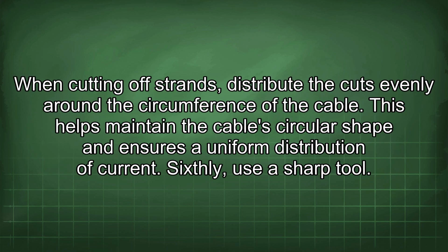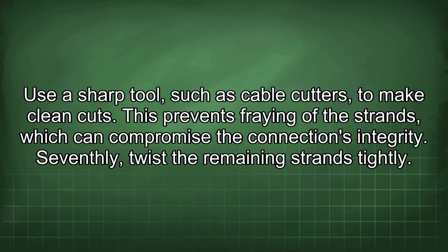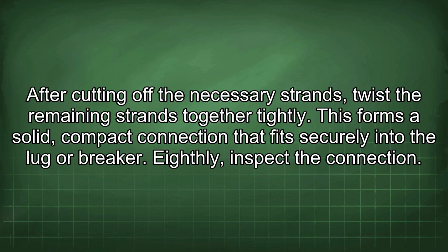When cutting off strands, distribute the cuts evenly around the circumference of the cable. This helps maintain the cable's circular shape and ensures a uniform distribution of current. Sixthly, use a sharp tool. Use a sharp tool such as cable cutters to make clean cuts. This prevents fraying of the strands, which can compromise the connection's integrity. Seventhly, twist the remaining strands tightly. After cutting off the necessary strands, twist the remaining strands together tightly. This forms a solid, compact connection that fits securely into the lug or breaker.